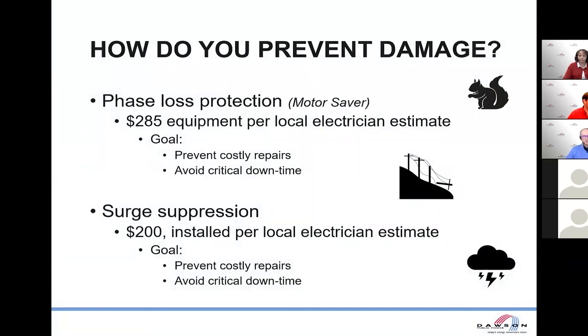Good morning. Basically, protecting your equipment is just an additional insurance policy. Some of the most common issues with the VFDs or just your control panel out in the field are somewhat preventable from a protection aspect. Things are going to happen on the power lines out beyond our control, beyond your control. As far as the motors themselves go, something called a motor saver, which is a trademark name of a piece of equipment, will protect against under voltage, phase loss, and a variety of other issues.